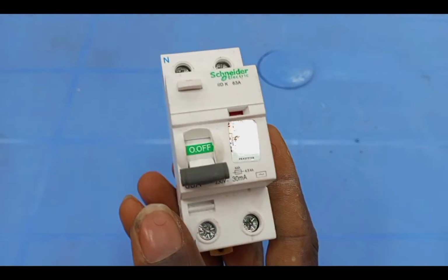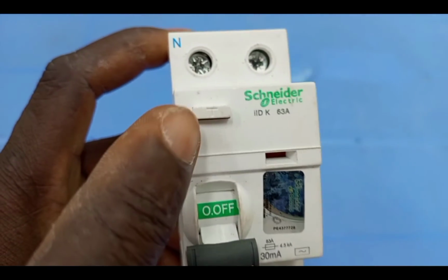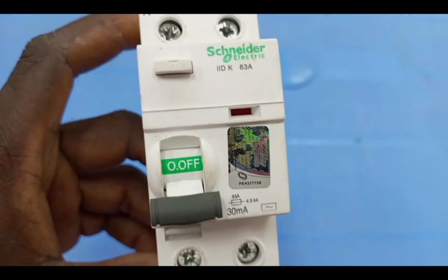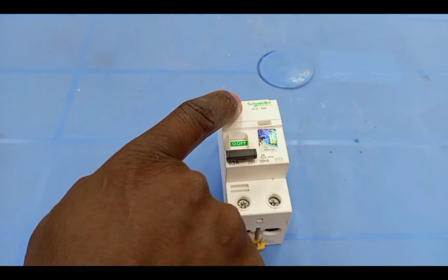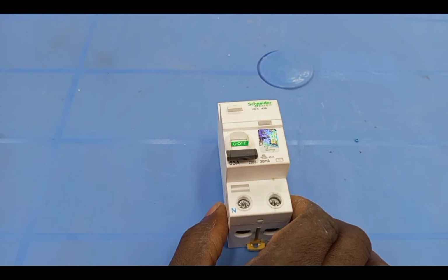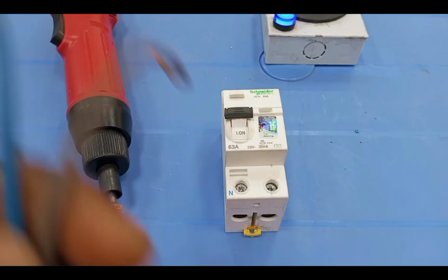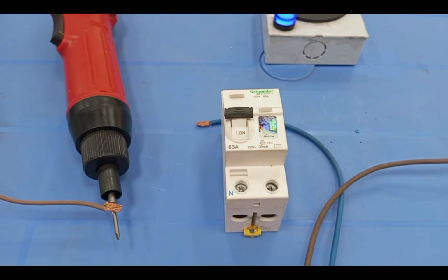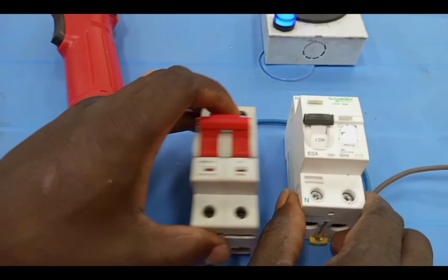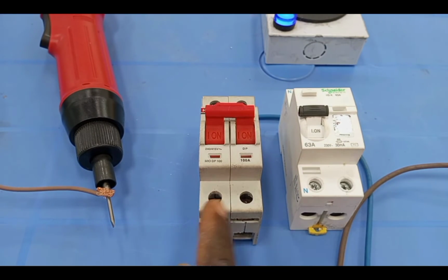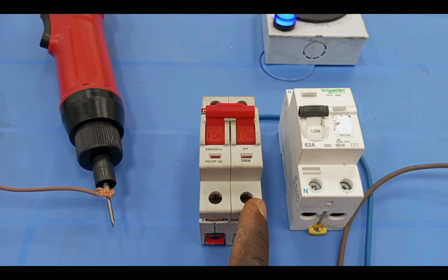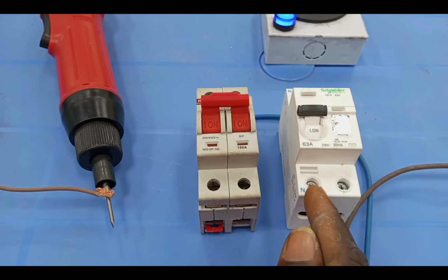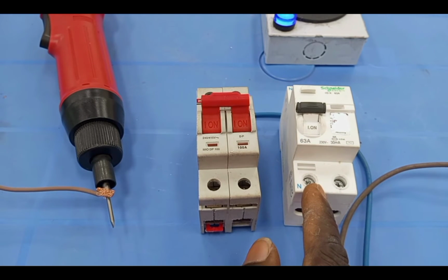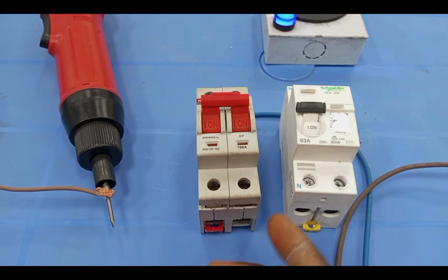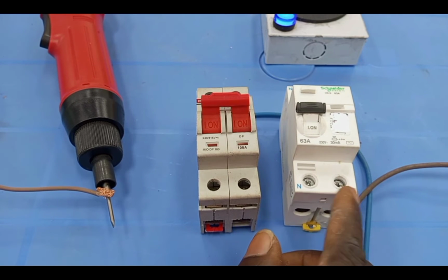Normally, when you buy an RCD, there should be a test button that you can use to test if the RCD is working. If you want to use this to test, then you have to connect supply to the RCD. Okay, so before I connect these wires, one important thing that you have to know is that unlike the miniature circuit breaker, that you can connect any of the cables to any of the terminals, in the case of the RCD, there is a place where you must connect your neutral, except you have an RCD that doesn't have any indication at any of the terminals. Blue is my neutral line.